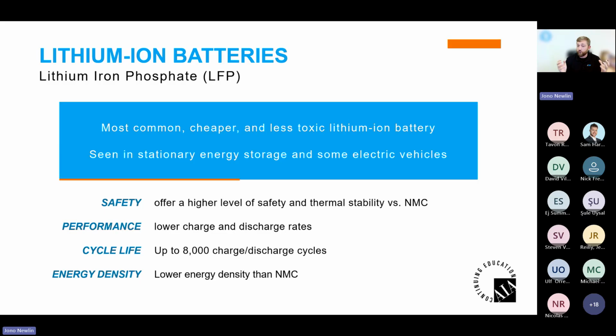NMC cells engulf quickly and have flame present when they go into thermal runaway because they have their own ignition source. LFP is more stable; it does off-gas some toxic flammable gases, but it's not as unstable as NMC. For stationary storage, you're dealing with larger quantities, so you want something stable that won't cause a big event if there's a thermal runaway, something you can mitigate and maintain, but more on that in a second.